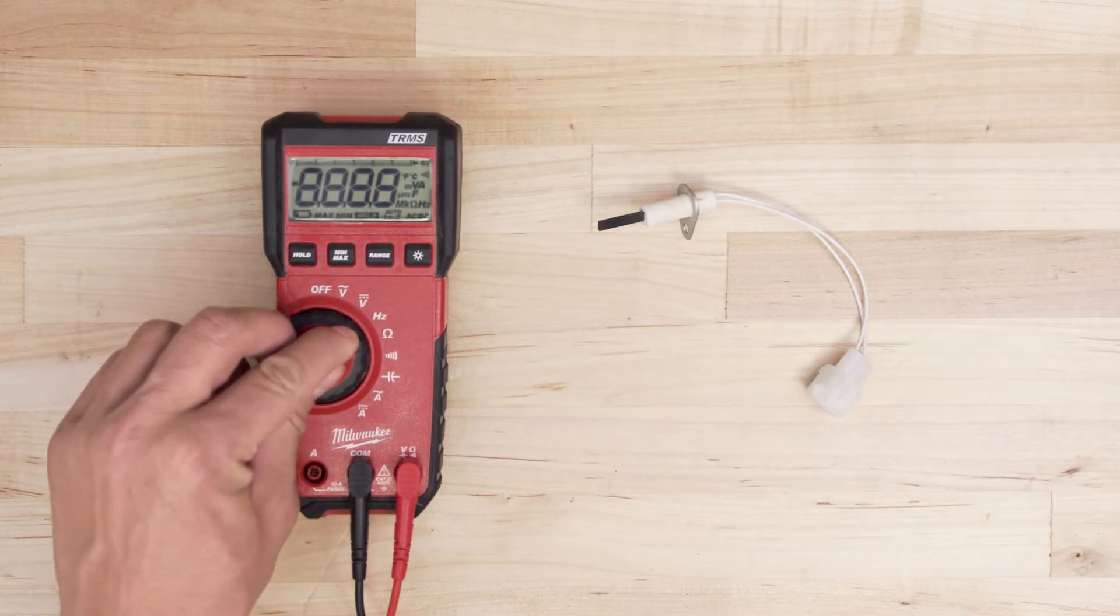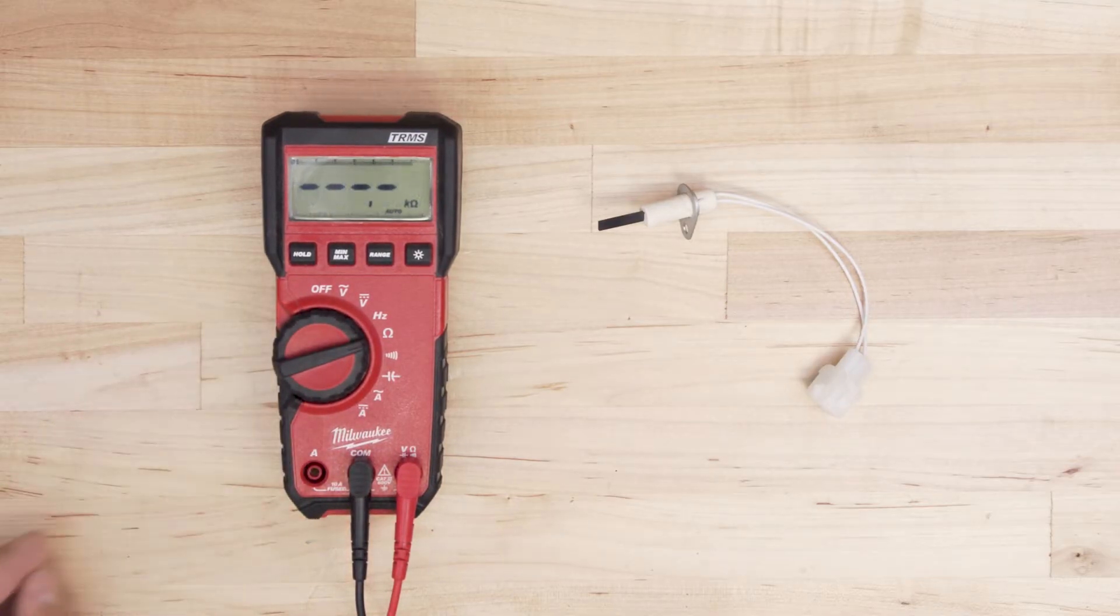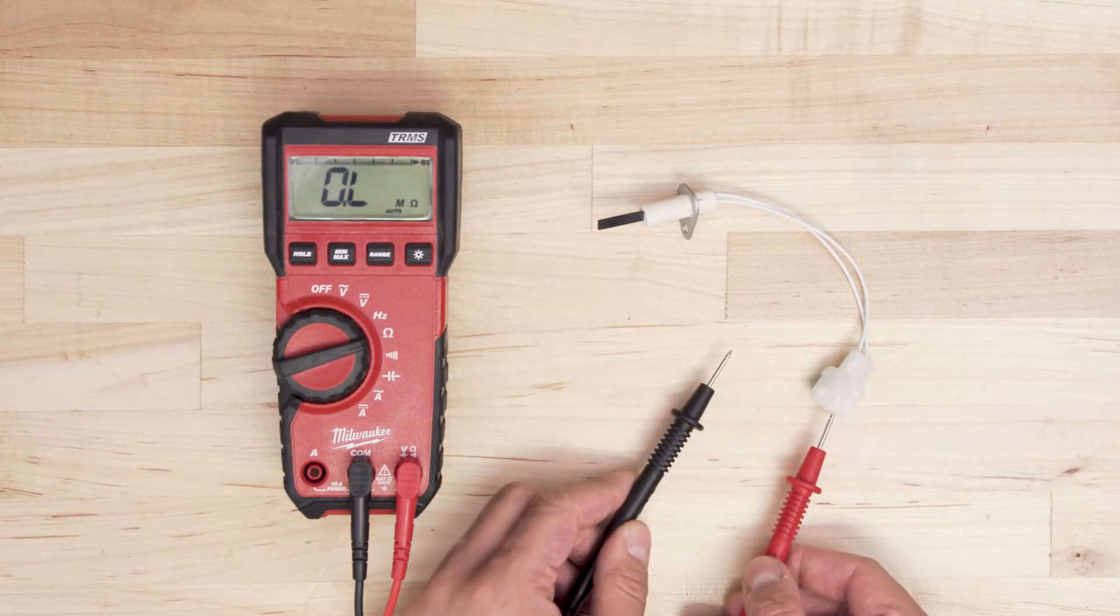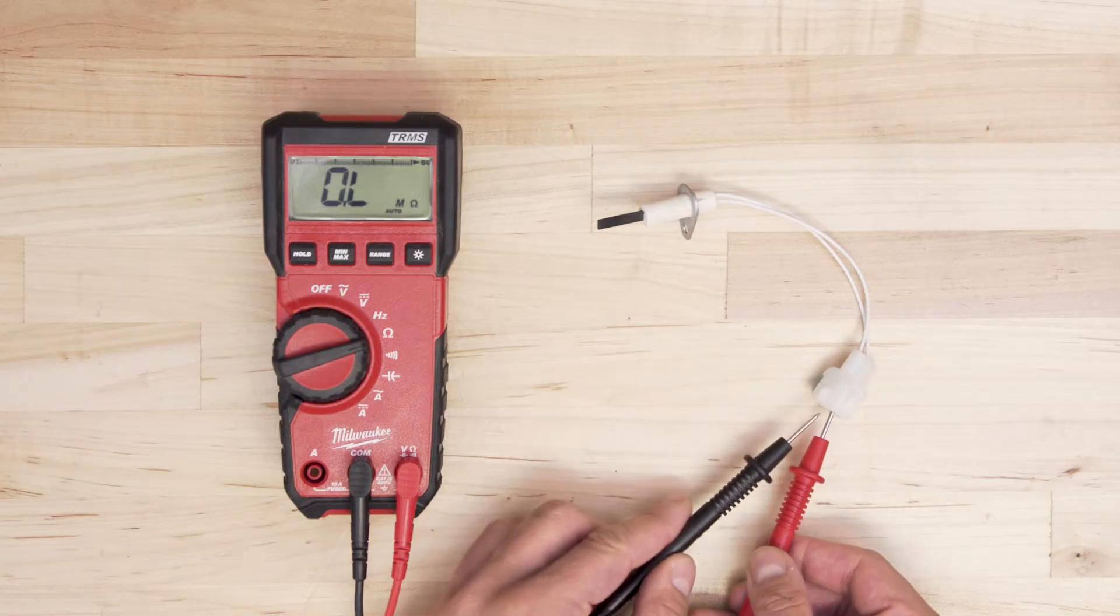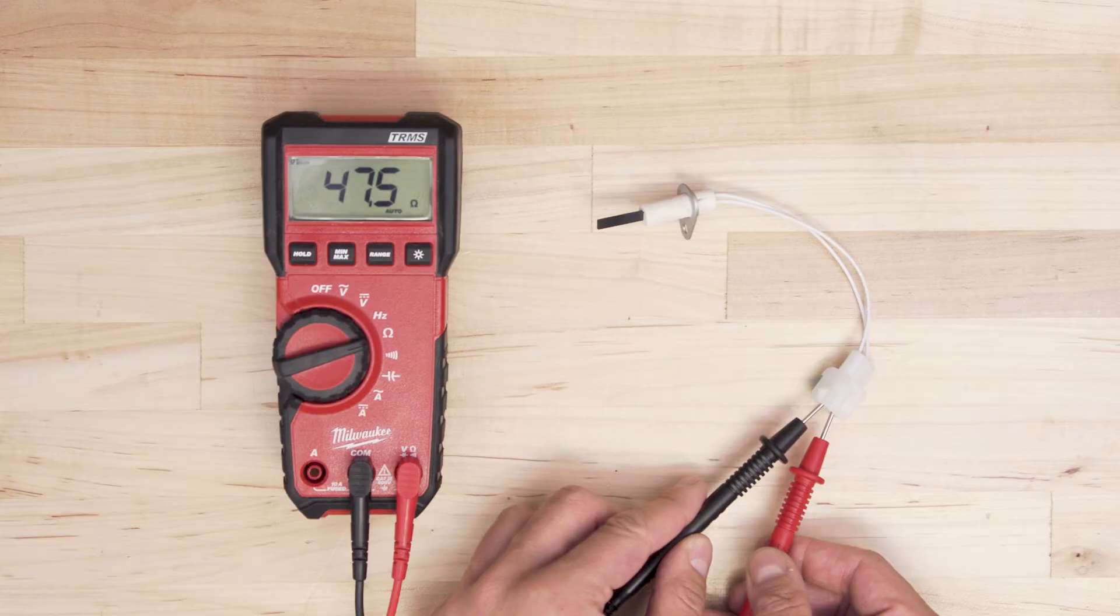Take the multimeter and set it to the lowest ohms of resistance. Now touch the probes to each terminal. If the igniter has continuity, your multimeter should read anywhere from 30 to 200 ohms.